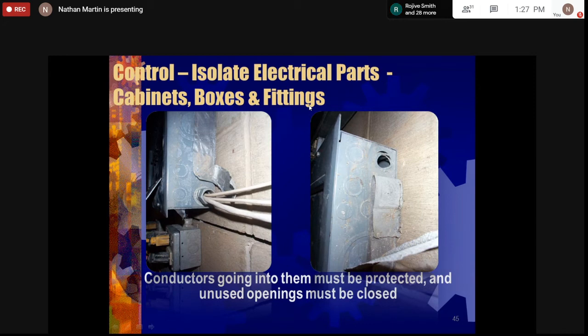The purpose of having the compression connector or bonding nipple is to provide mechanical protection. In the diagram on the left, someone could go there and pull the cables right out of the box. There's no protection provided for the terminals, the termination, or the cables.